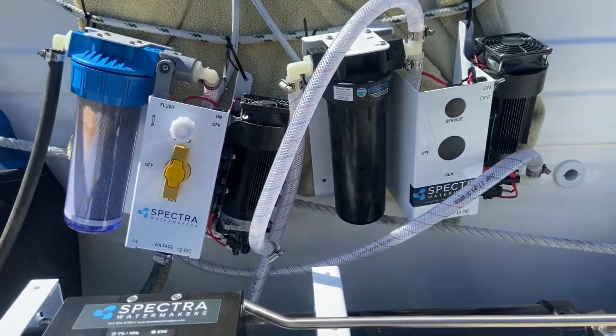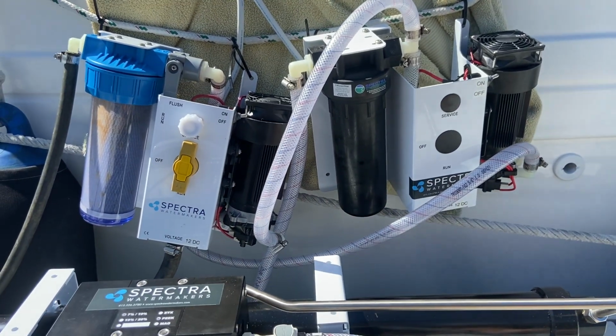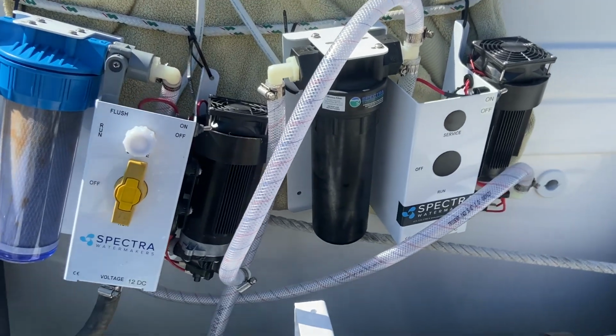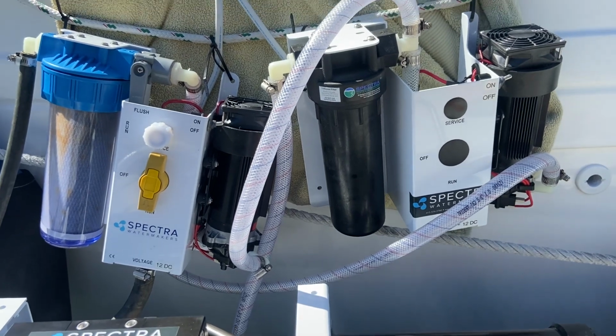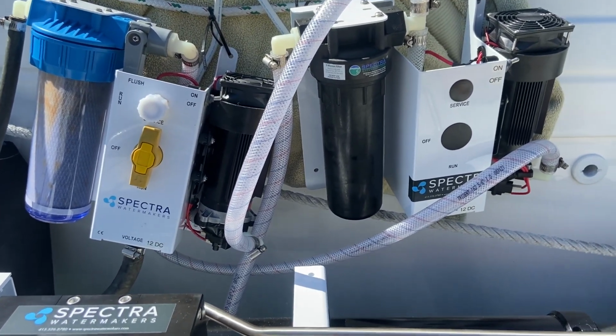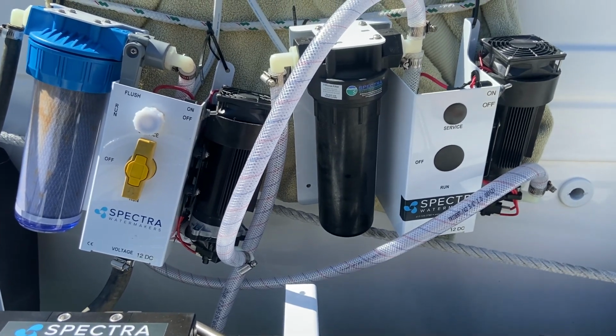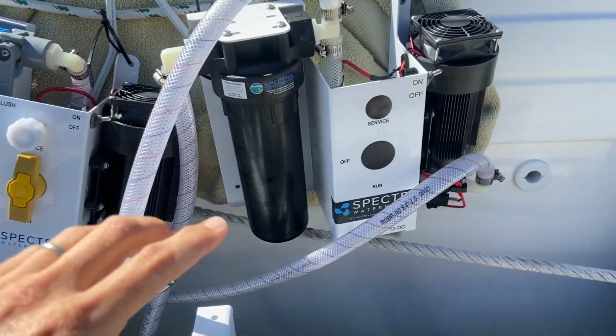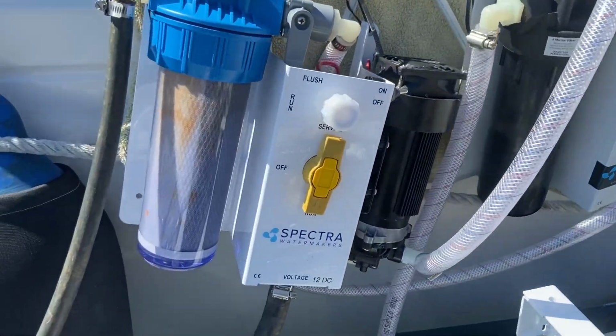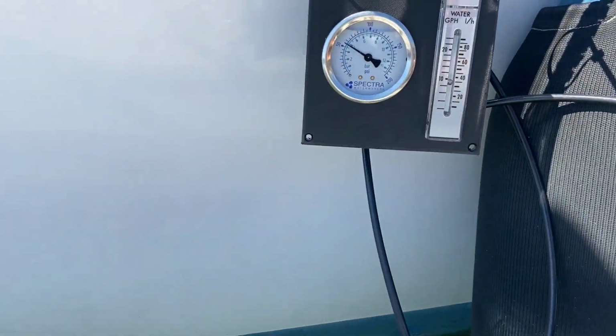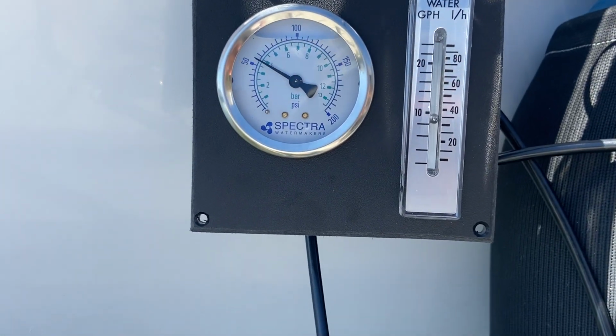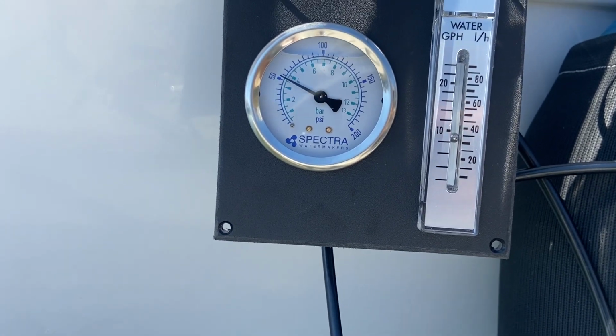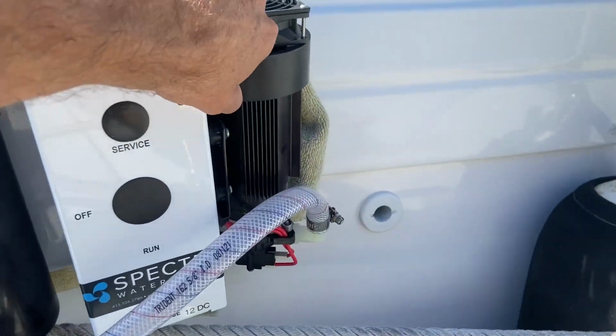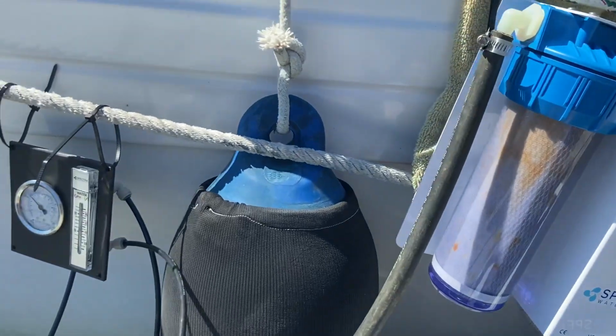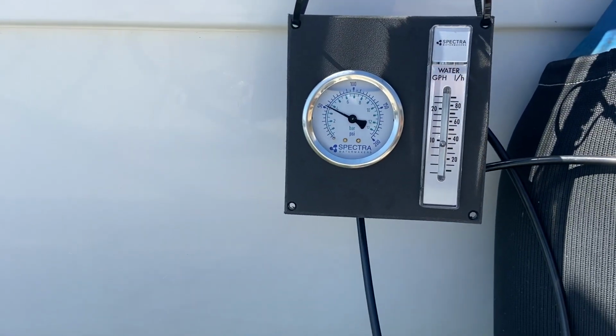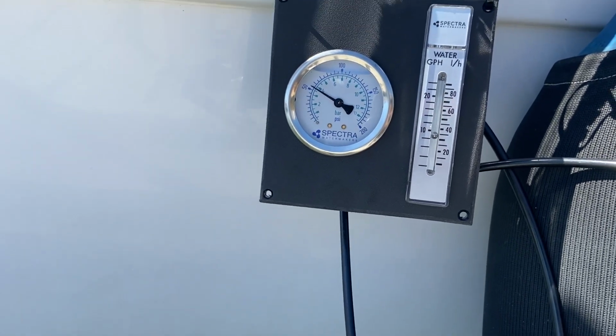So the beauty about this system is the two pumps giving you full redundancy. You can have a full feed pump failure and still be making 9 or 10 gallons an hour. Also, if you've got very saline water or very cold water, that'll drive your feed pressures up too high. So you can run on one pump and get the feed pressures down and still be operational. So let's do that right now. Let's turn off feed pump module B. We're just running off of A now. And we see our feed pressure drop to about 55. And we're making about 9 gallons an hour. And let's turn B back on, A off, and the exact same thing. We're at about 55 psi, about 9 gallons an hour.